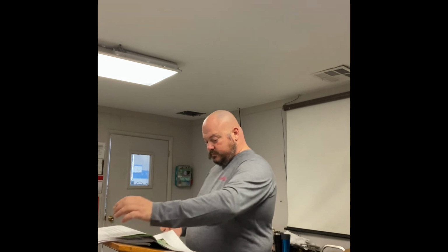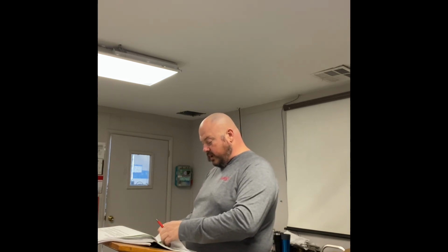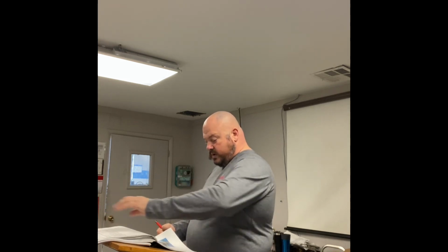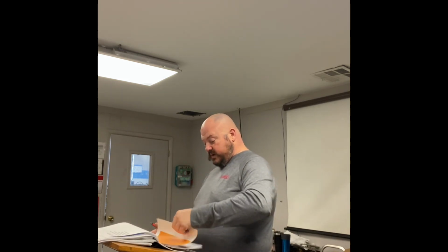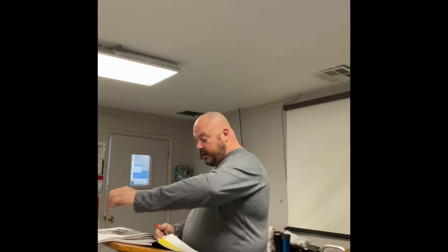We just go through this. The rest of this is really going through just your damages, talking about how to prevent the flooded starts and flood backs. You know, we can get into crankcase heaters. Think of it like a block heater. If you live in Alaska, you better plug your engine in or it's going to freeze up at night. Okay, well, we're doing refrigeration systems and you've got a walk-in freezer and you're going to run it in the middle of winter, you probably want to have a crankcase heater in it to keep everything from getting frozen up. Okay? Slugging has great pictures on it. Through that there, there's a great picture of that scroll compressor that's exploded again. Overheating. Getting more in-depth pictures in it.